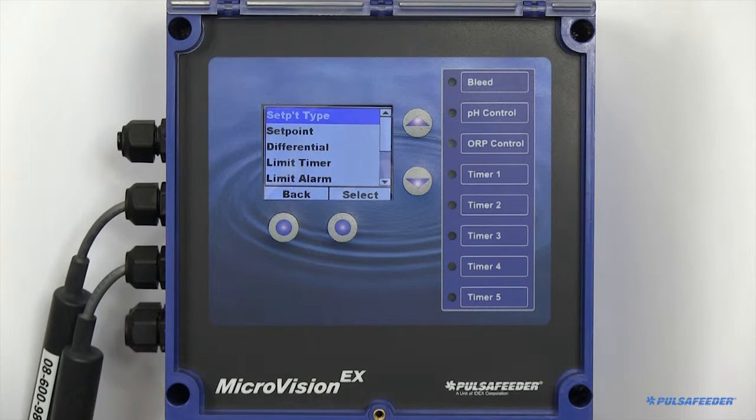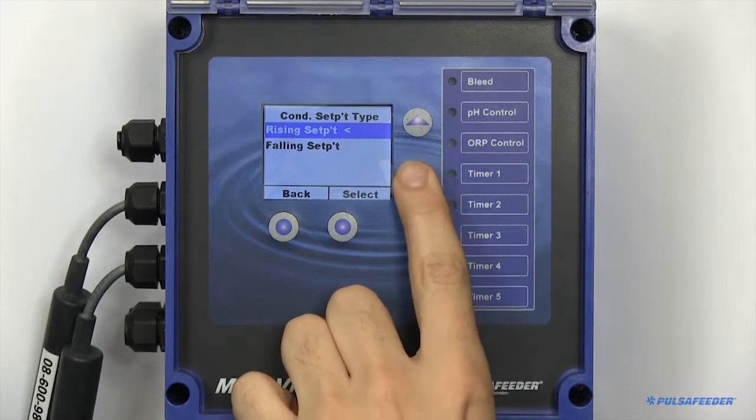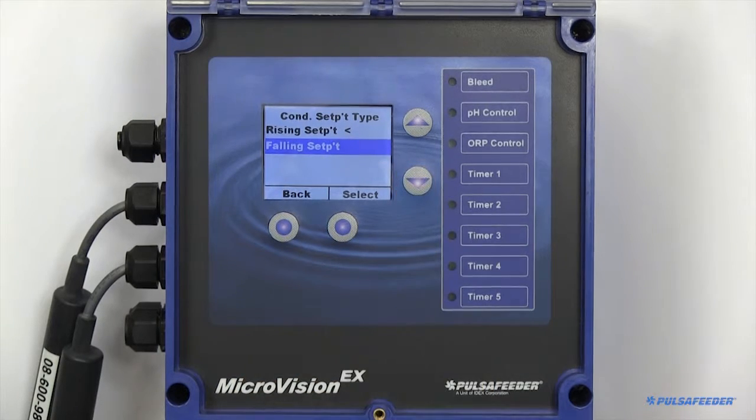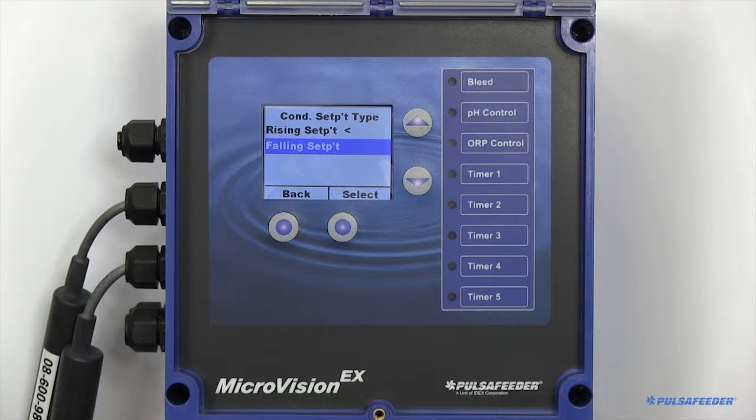To set up your conductivity probe, you need to choose your set point type. You can choose between rising or falling. Rising type means that the output activates when the input goes above the set point. Falling type activates the output when the value goes below the set point.